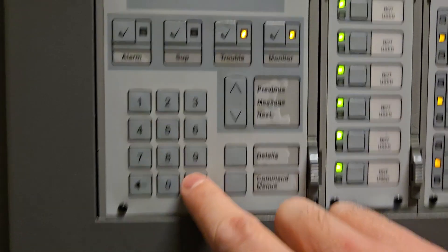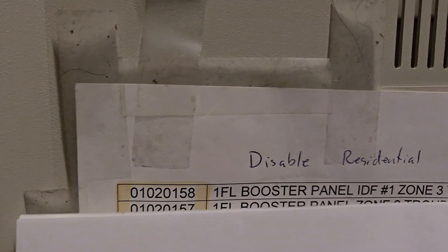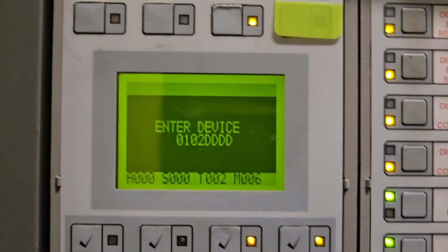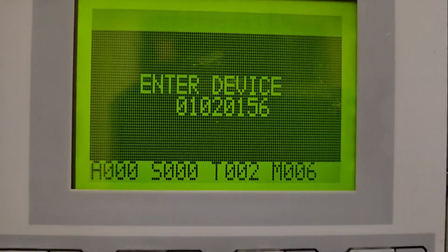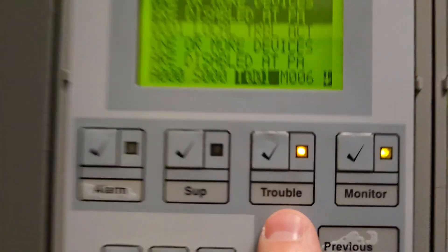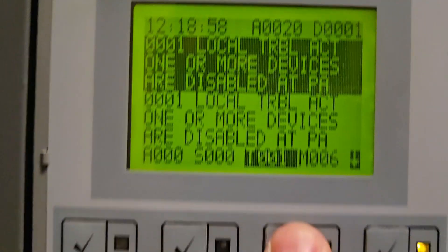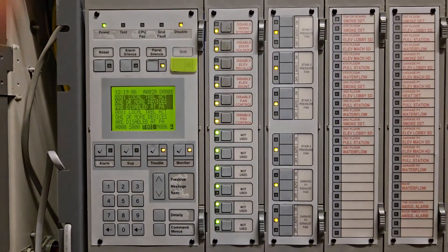I hit enter and it goes down to two troubles. Then the last one: 01-02-0156. I already have zero one zero two, put in zero one five six, hit enter, and now I'm down to one trouble — right where I originally started. I'll hit command menu and scroll through troubles: I only have the very first trouble, 'one or more devices are disabled,' which is from those pre-existing disable buttons. The first floor troubles are no longer there — they're cleared. Now I can go ahead and test the first floor horns and strobes.